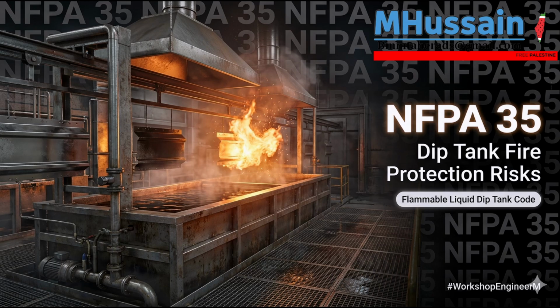Now, what about moving liquids by pressurizing a tank and pushing the liquid through the pipe with gas? Pressurized transfer. That is permitted, but the code introduces a severe restriction based on the fire triangle. The fire triangle: fuel, heat, oxygen. Right. If you are using pressurized gas to push a highly flammable Class I liquid through a pipe, you absolutely cannot use compressed air. Because air is 21% oxygen. Exactly. If you use compressed air to push a volatile solvent, you are actively mixing the fuel with pressurized oxygen inside a steel pipe.